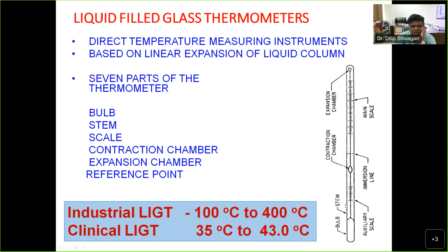It means that, suppose you are measuring at 40, you have to immerse up to 40 degrees Celsius. If you are measuring at 60, you have to immerse up to that. You need a certain depth of bath, and most of the time I observed that they don't have adequate facility to immerse to this depth of liquid, and then end up doing a partial measurement.